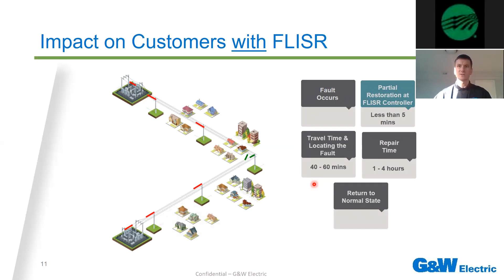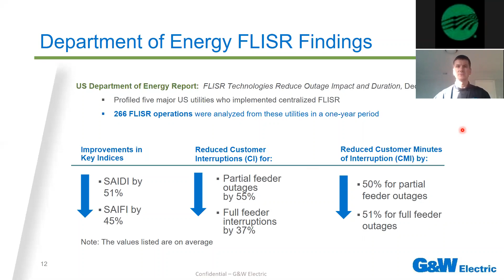I have 2 slides on the monetary benefits here. The first looks at indices for duration and frequency of outages. The U.S. Department of Energy issues these reports, I want to say every 5 years. This one is a bit older, from 2014, but it looked at 266 FLISR operations, and you can see the improvements. Those are average improvements: duration of outages went down by 51%, frequency of outages went down by 45%, and customer interrupted minutes go down as a result. So there's proof over time and across different utilities that FLISR improves your reliability.